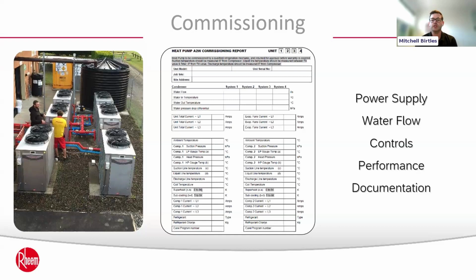In the middle of the screen, you can see a snapshot of what we look at, which includes electrical inputs and outputs, refrigerant pressures and temperatures, water temperature differentials, and sensor testing. Controller settings that have been adjusted are also important to note. We keep these files on hand in dedicated project folders to refer to in the event of any site issue, and the site should also keep a copy on hand as well.